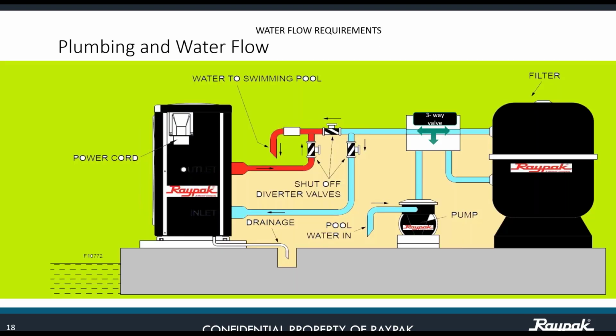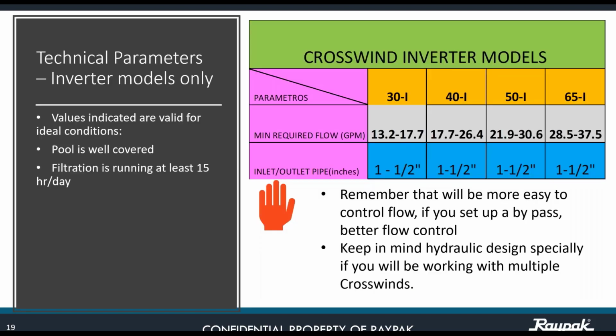So let's see the water flow. Water flow is a very simple unit to install. We have the two isolation valves right here. Bypass. Always remember, it's good to have a bypass when you do any type of installation, regardless if this is a gas heater, a heat pump series 40, or a Crosswind. If you have a proper bypass, you're going to be able to control the flow, especially if you're working with variable speed pumps. So let's see the parameters, the flows.